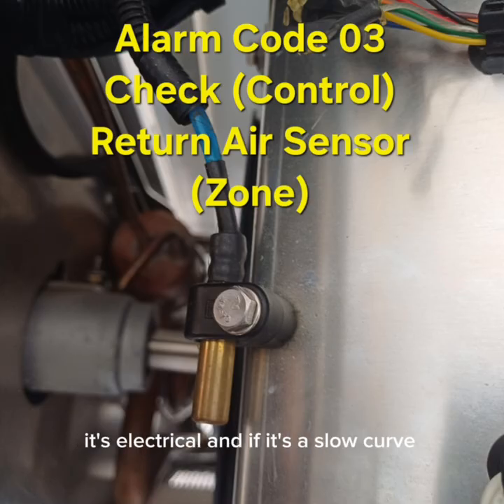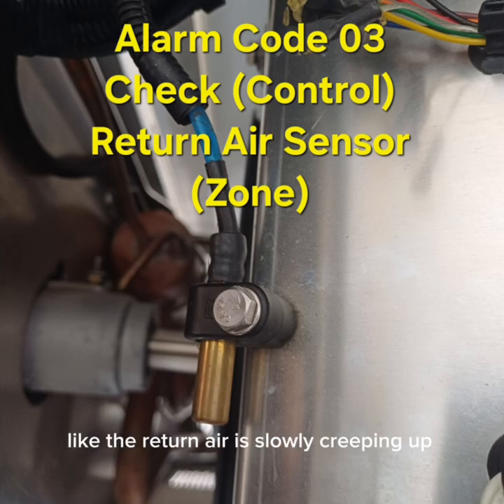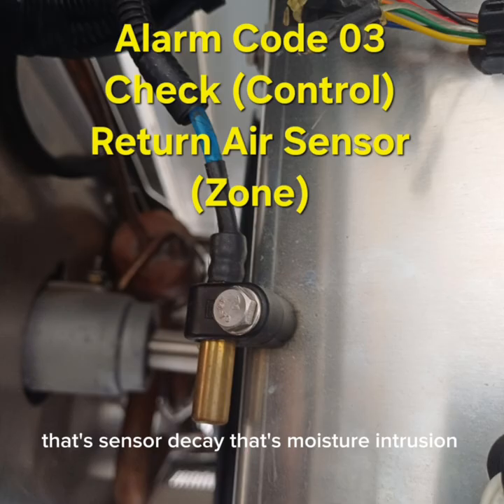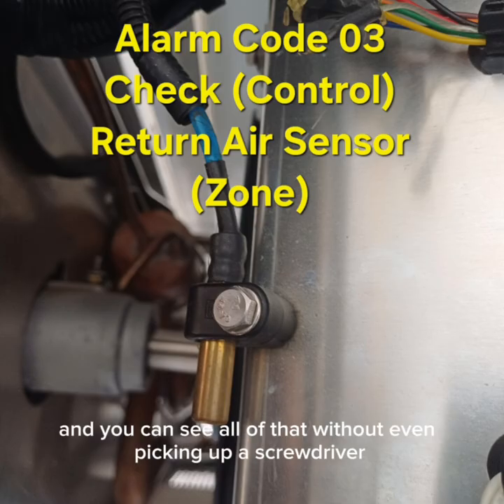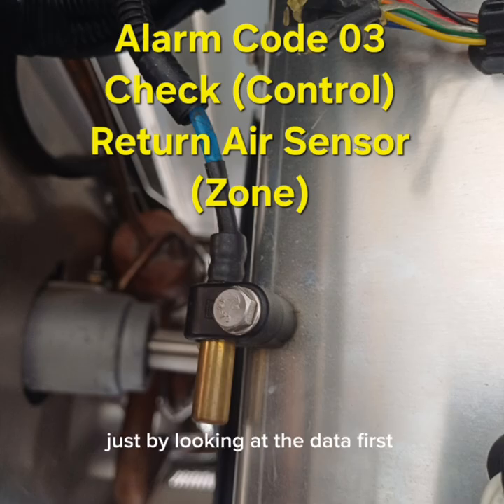And if it's a slow curve? If you see it drifting slowly over time, separating from the other sensors, like the return air is slowly creeping up while the discharge air stays flat, that's sensor decay. That's moisture intrusion. That's a soft failure. And you can see all of that without even picking up a screwdriver, just by looking at the data first.